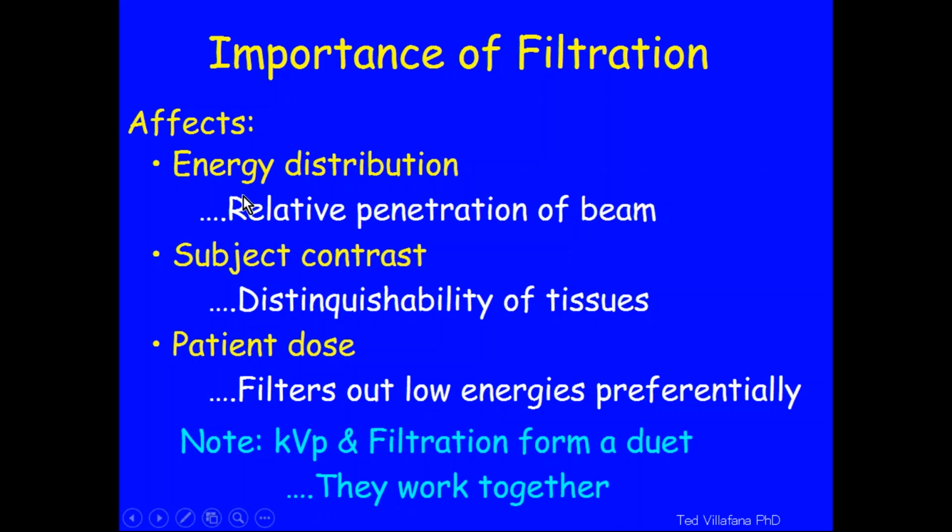We know that the energy distribution is affected by the filtration. The penetration of the beam is affected by the filtration. The contrast is affected because filtration changes energy. And if you change energy, you change contrast, and they go in opposite directions. And then I wanted to especially emphasize the patient dose. We'll talk about that right now.